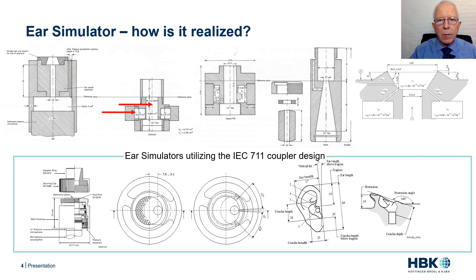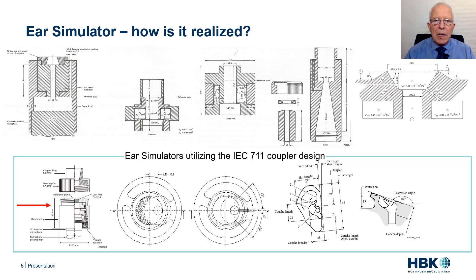Some of the first ear simulators intended for measurements of earphones were developed in the early 1960s. The Zwislocki coupler depicted in the slide is an example of one of these early ear simulators. In the Zwislocki coupler, the location of the cavities as well as the cylindrical shaped ear canal can be observed. In the early 1980s, the 711 coupler was established, and the actual design of the coupler was inspired by the Zwislocki coupler.